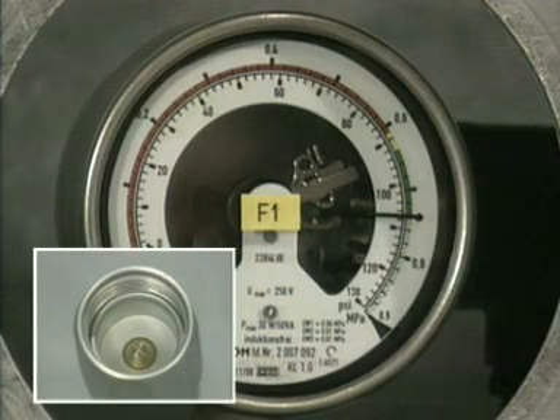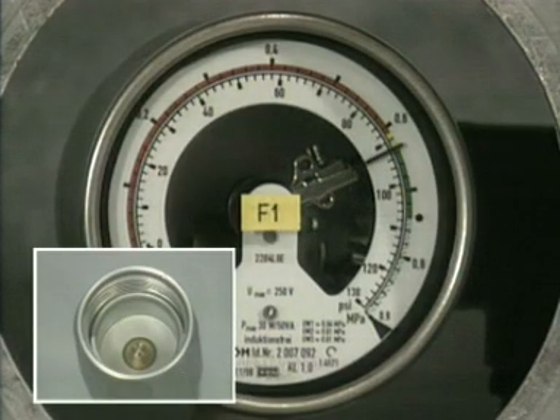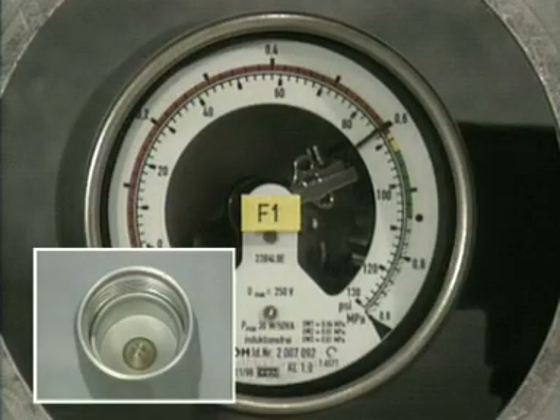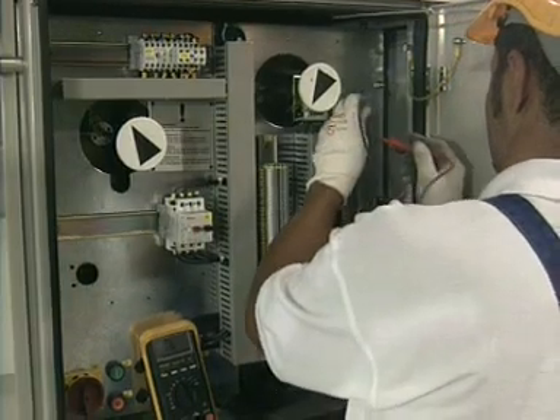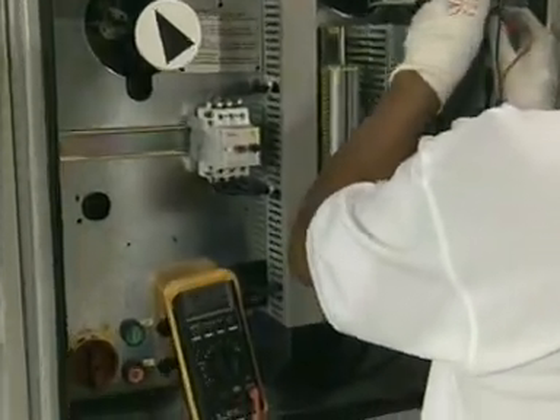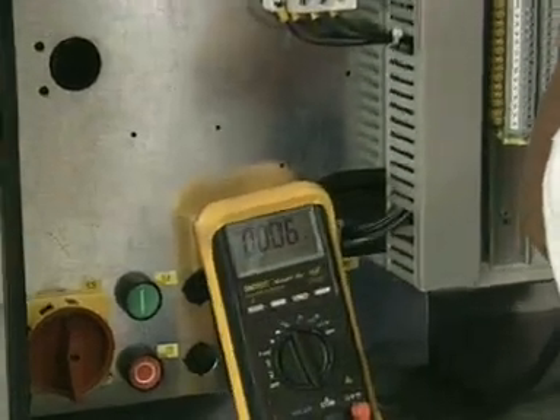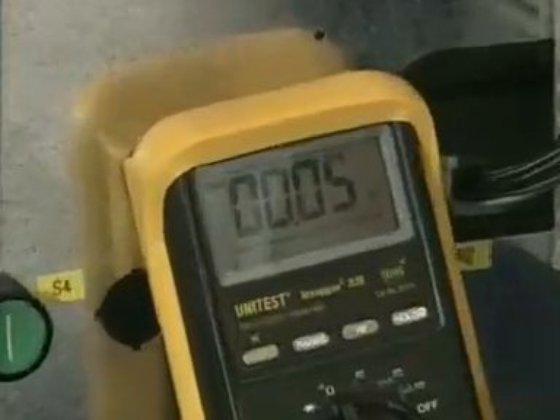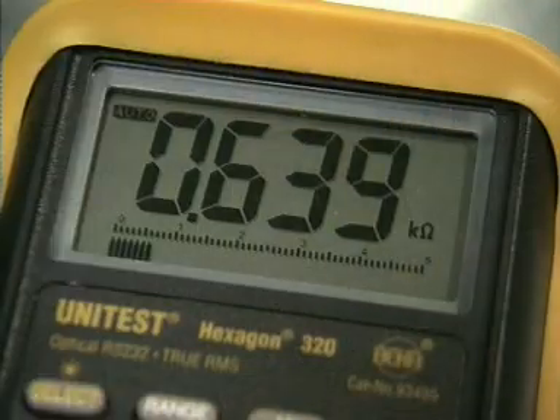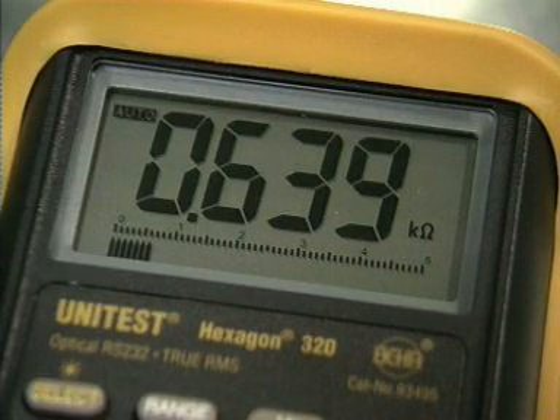Reduce the gas pressure gradually by pressing one of the poppet valves until the various SF6 warning levels are reached. Also check the density monitor contacts for continuity. Then measure the resistance of the anti-condensation heater at the terminals in the mechanism and check it against the routine test certificate.